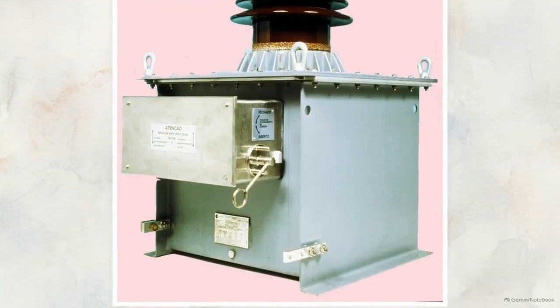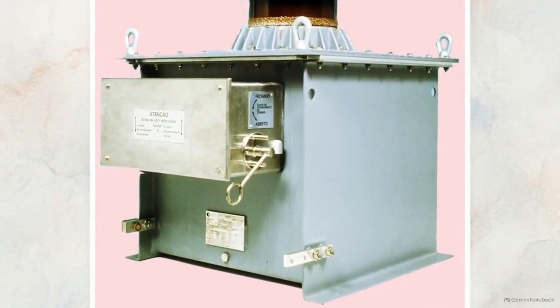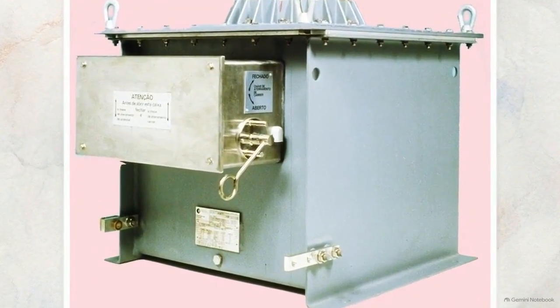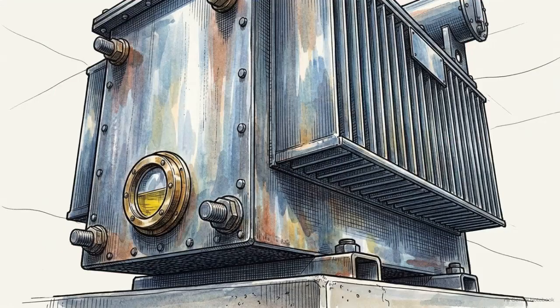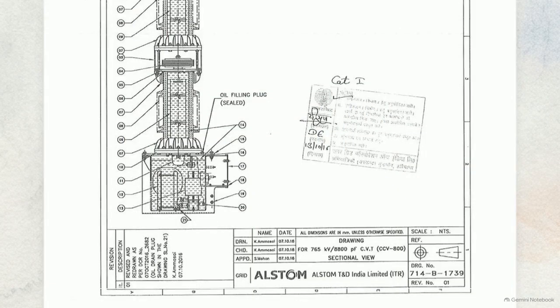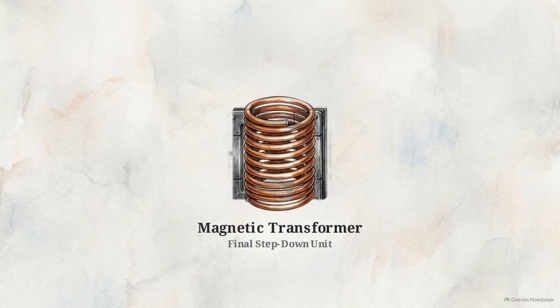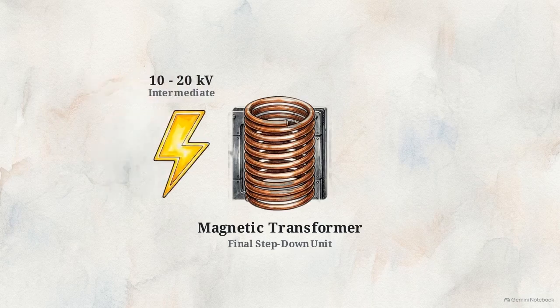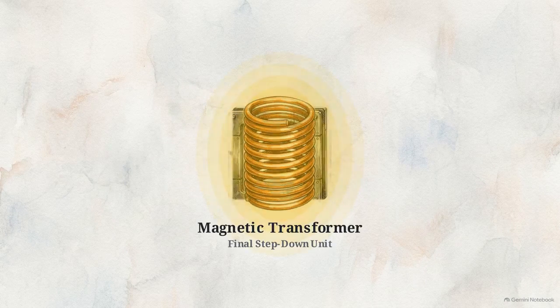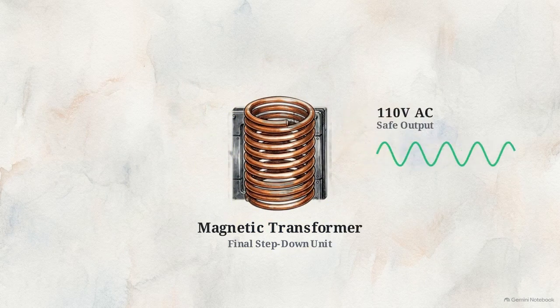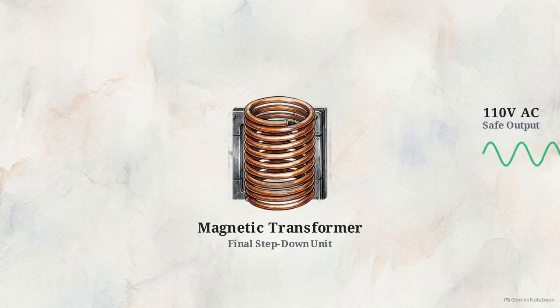That intermediate 20 kilovolts travels down the column and enters the solid metal tank at the base of the tower. This base is called the Electromagnetic Unit, or EMU. Returning to the schematic of the base tank, we see a shift in technology. Housed at the bottom is a medium voltage transformer. Because the voltage is already reduced by the tower, a smaller, safely insulated magnetic transformer performs the final step down to the required 110-volt output.